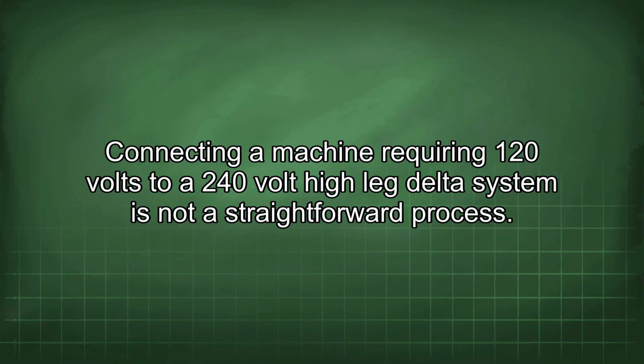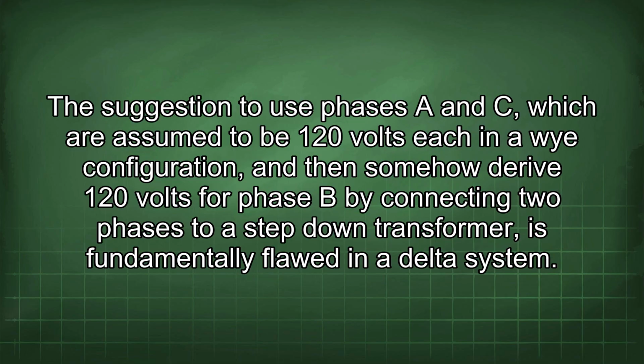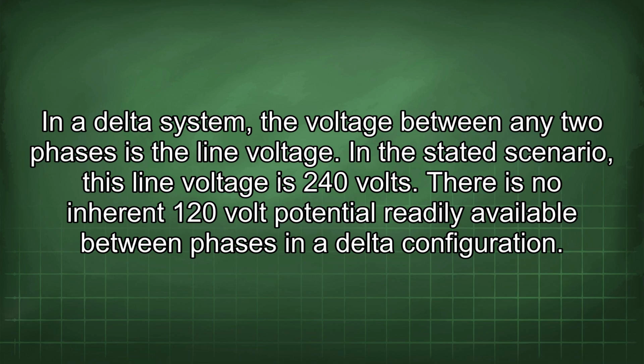Connecting a machine requiring 120 volts to a 240 volt high-leg delta system is not a straightforward process. The suggestion to use phases A and C, which are assumed to be 120 volts each in a Y configuration, and then somehow derive 120 volts for phase B by connecting two phases to a step-down transformer, is fundamentally flawed in a delta system. In a delta system, the voltage between any two phases is the line voltage. In the stated scenario, this line voltage is 240 volts.